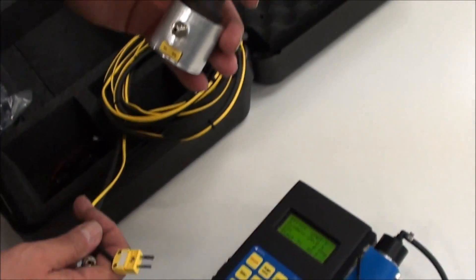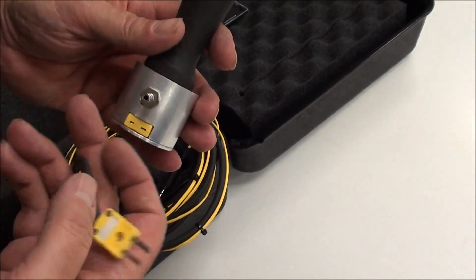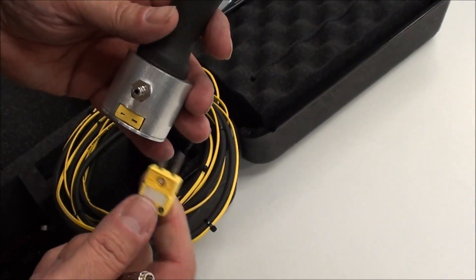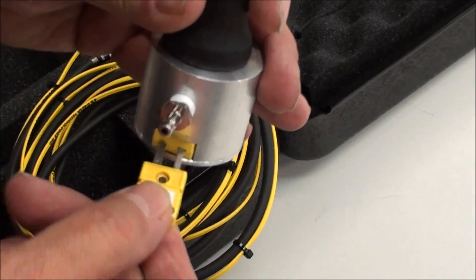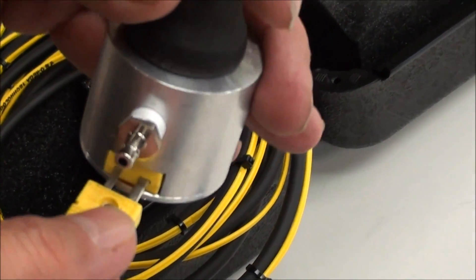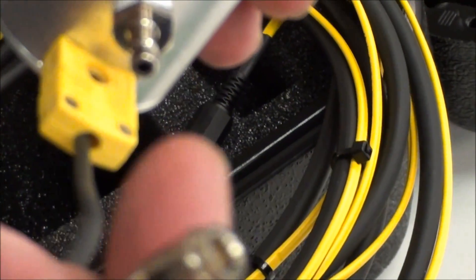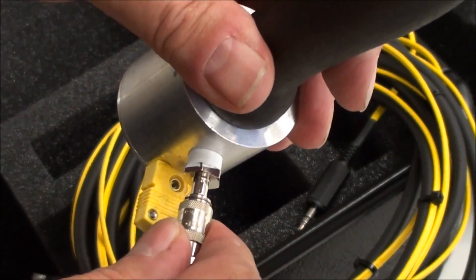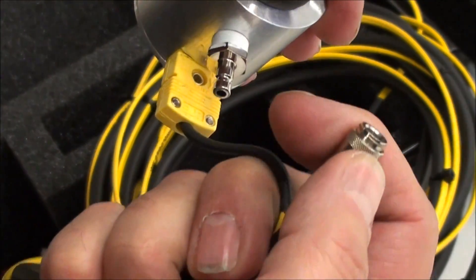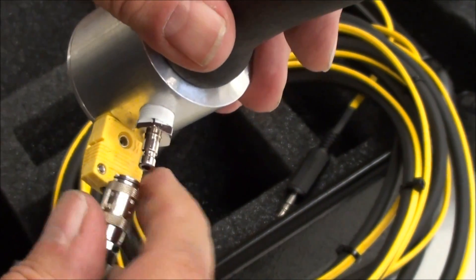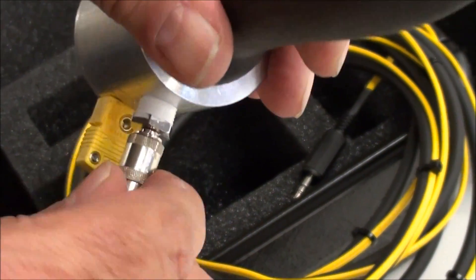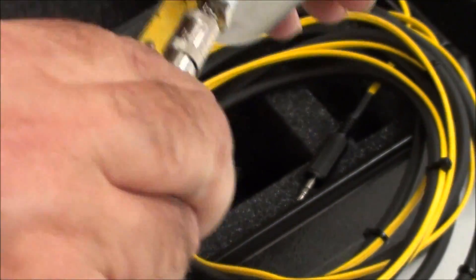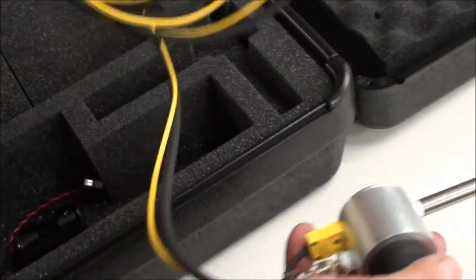You have the probe connection, the thermocouple, and the gas fitting. The thermocouple plugs in. It's keyed, so you can't accidentally put it in the wrong way. You can only put it in one way. Then, you have your gas connector. If you go to press the gas connector on, and it won't go on, you may have to just pull the collar back, and let it lock open again. Then, you just press it on, and the collar goes forward, and it locks into place. Now, your probe is connected.